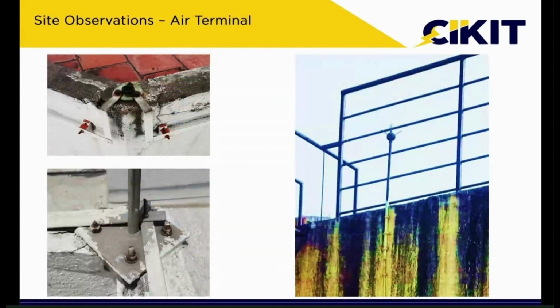These are some of our site observations. Here you can observe that in the first image there is no air terminal at all. In the second image they have placed the down conductor on the plate directly. There is no proper connection between the air terminal and the down conductor. In the third image, they have placed this lightning arrestor, then they have installed this handrail. But the air terminal should be the topmost point. Here the handrail is the topmost point. Even if any lightning approaches, it will strike on this handrail only. It won't strike on this air terminal. So the purpose itself is not solved.